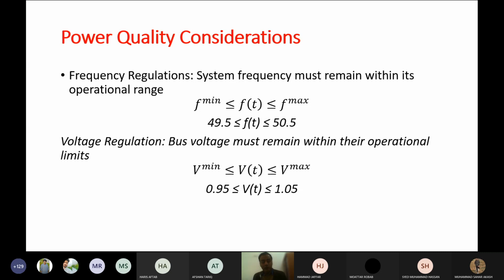Similarly, the voltage in per unit for a high voltage system should not be lesser than 0.95 per unit and should not be greater than 1.05 per unit. What this actually means is that in a higher voltage transmission network, you have 5% voltage flexibility. What does this 5% mean? It means your voltage should not exceed 525 kilovolt in a 500 kilovolt transmission line, and should not be less than 475 kilovolt in your 500 kilovolt line. Fine.